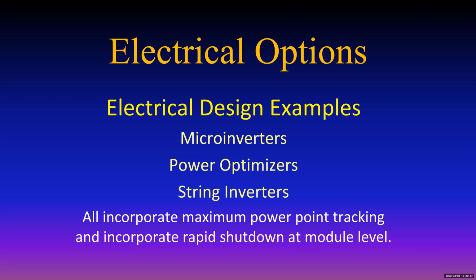And rapid shutdown at the module level, that's another advantage. That's been pretty important since 2017, even 2014, but it's getting tighter and tighter. And now is necessary to, as of 2020, you have to shut down within the boundaries of the array. No more electricity outside where the modules themselves are. And you need to do that fast if you have an emergency. The firemen or whatever the first responders are, have to have a switch somewhere that they can flip that thing, and you lose all power coming out of the array within a couple of seconds.